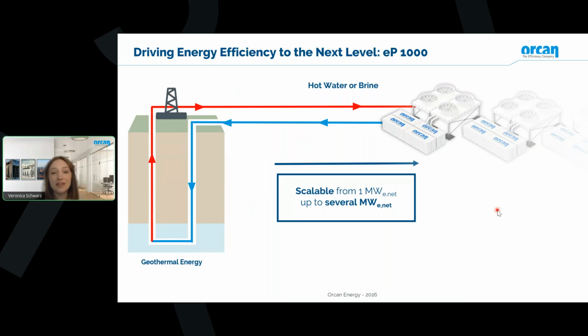The interesting thing is we developed this especially for geothermal applications. In this case, we can go into the machine directly with the geothermal brine. How we do that is we have a specialized evaporator for every application. The rest is still completely standardized and the same. The only thing that's customized is the evaporator, to make it possible to go into the machine directly with the geothermal brine, to take advantage of the temperature as much as possible and get higher efficiencies.